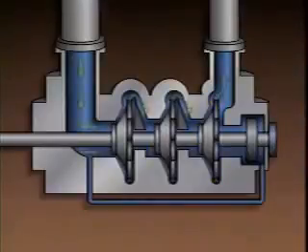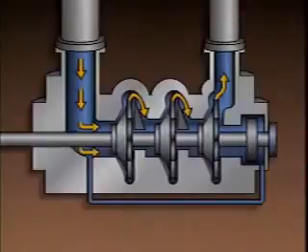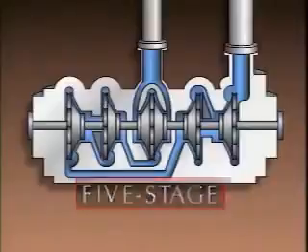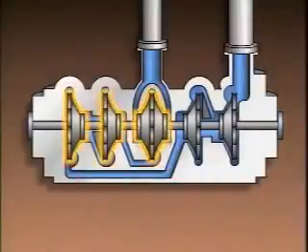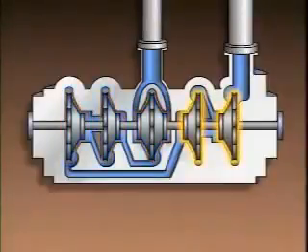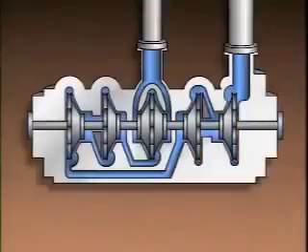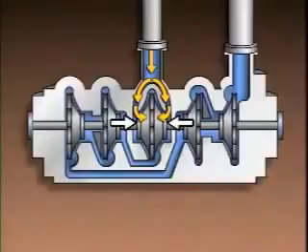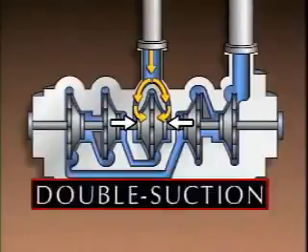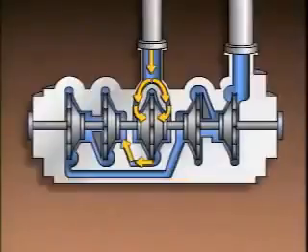This is a five-stage pump. It has five impellers and five volutes, with the first three stages located in one section and the fourth and fifth stages in another. In this pump, liquid enters through the suction and flows into the impeller of the first stage. This impeller has a suction eye on both sides and is often called a double-suction impeller. From the discharge of the first stage volute, the liquid flows into the second stage suction eye.